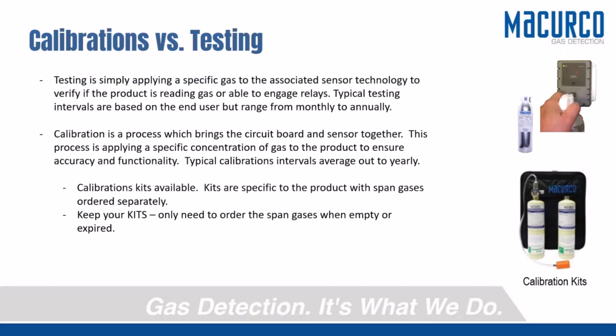The biggest question when a new install happens is, do I need to calibrate it? The answer is, per our user manual, you do not have to calibrate it. However, we are not the AHJ, so we don't make that call at the time of install. So if you have a new gas detection system going in, and you can pick any type of application or any type of gas, if your AHJ or an inspector says we want to see it calibrated, there's a couple things you could do. You could show them in the manual saying, hey, these came factory calibrated.